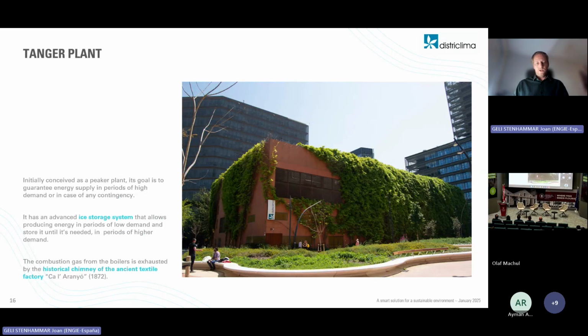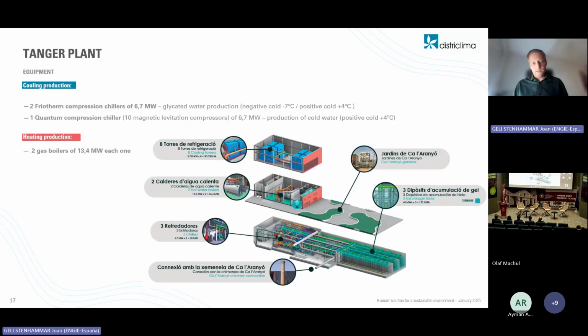Now, the second plant, built around 2010, was planned to be a backup system that helps us always give continuous service 24/7. It is interesting because this plant includes an ice storage tank with a capacity of 2,500 cubic meters, which allows us to store around 120 megawatt hours. This storage tank is placed underground, and we can store ice because we have 3 chillers. 2 of them can either provide negative temperatures at -7 degrees, or just produce towards the network, producing positive temperatures at 4 degrees.